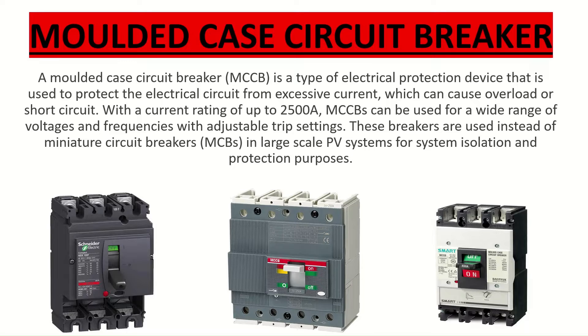The first slide is the definition of MCCB. A molded case circuit breaker, or MCCB, is a type of electrical protection device used to protect the electrical circuit from excessive current, which can cause overload or short circuit. With a current rating of up to 2500A, MCCBs can be used for a wide range of voltages and frequencies with adjustable trip settings. These breakers are used instead of miniature circuit breakers, MCBs, in large-scale PV systems for system isolation and protection purposes.